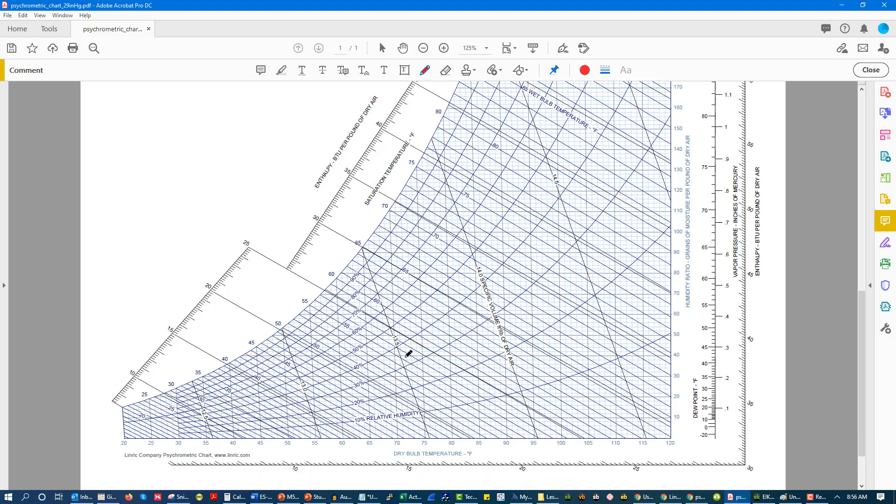So if we were sitting at 75-50, let's just do that, 75 degrees, 50% relative humidity. There's so many lines. Where do I draw this thing? Okay, 75-50%. So if we're here, then we can see what our humidity ratio is, we can see how much moisture we have, we can see what our wet bulb temperature is.